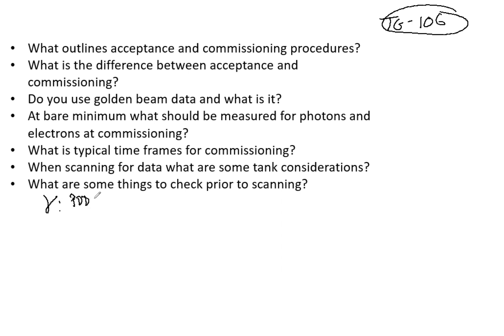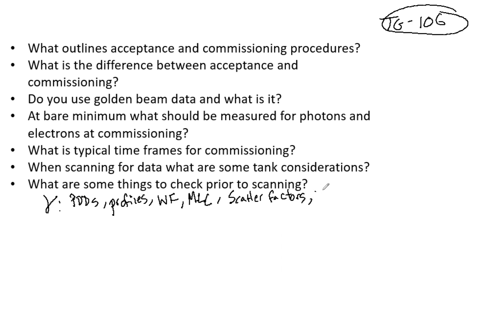At bare minimum for photons, you need percent depth doses, beam profiles (both inline and crossline), and wedge factors. You can think about what you'd need for an MU check for a photon field. You also need MLC data, including leakage, penumbra, how many MLCs you have, and the DLG. Scatter factors are also important, as are tray factors.